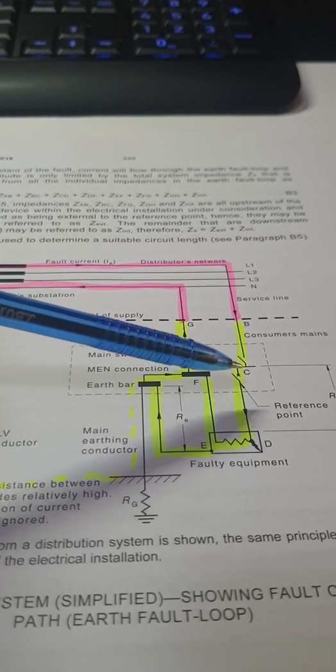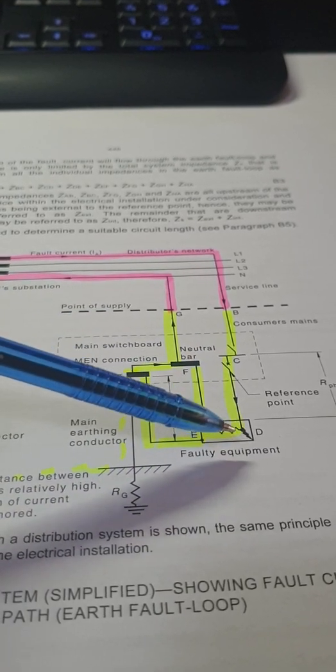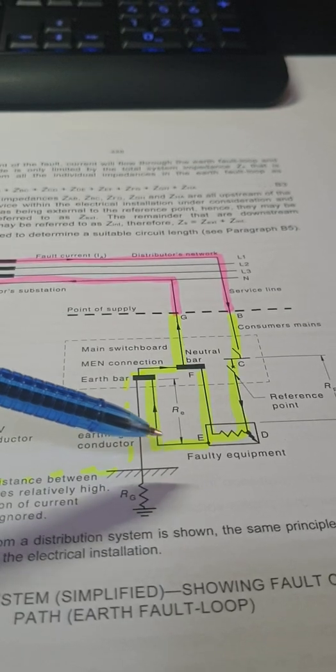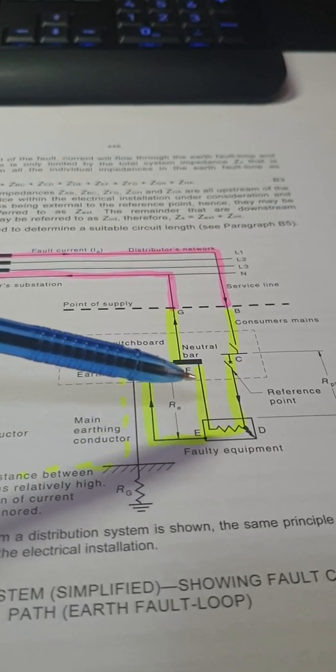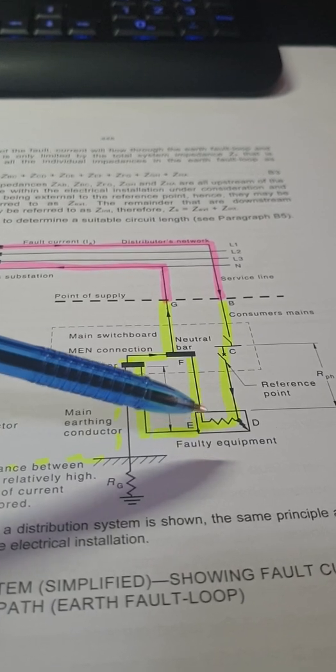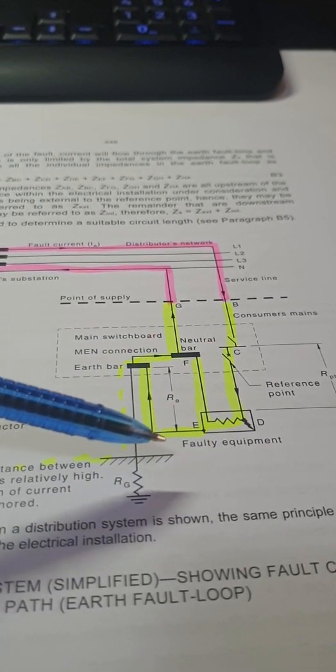When we get to this point here at the main switch, we then take it down through the sub circuit to the appliance. The faulty appliance. We then come back via the earth. This part here, which is a neutral, doesn't come into the fault.